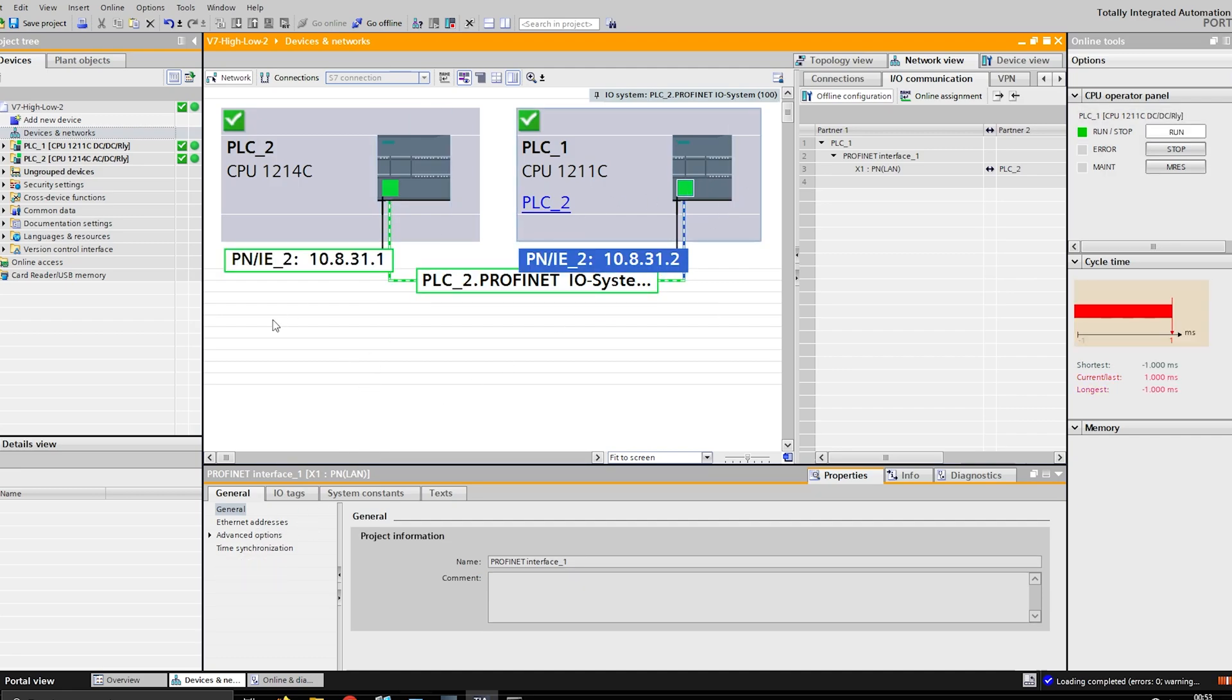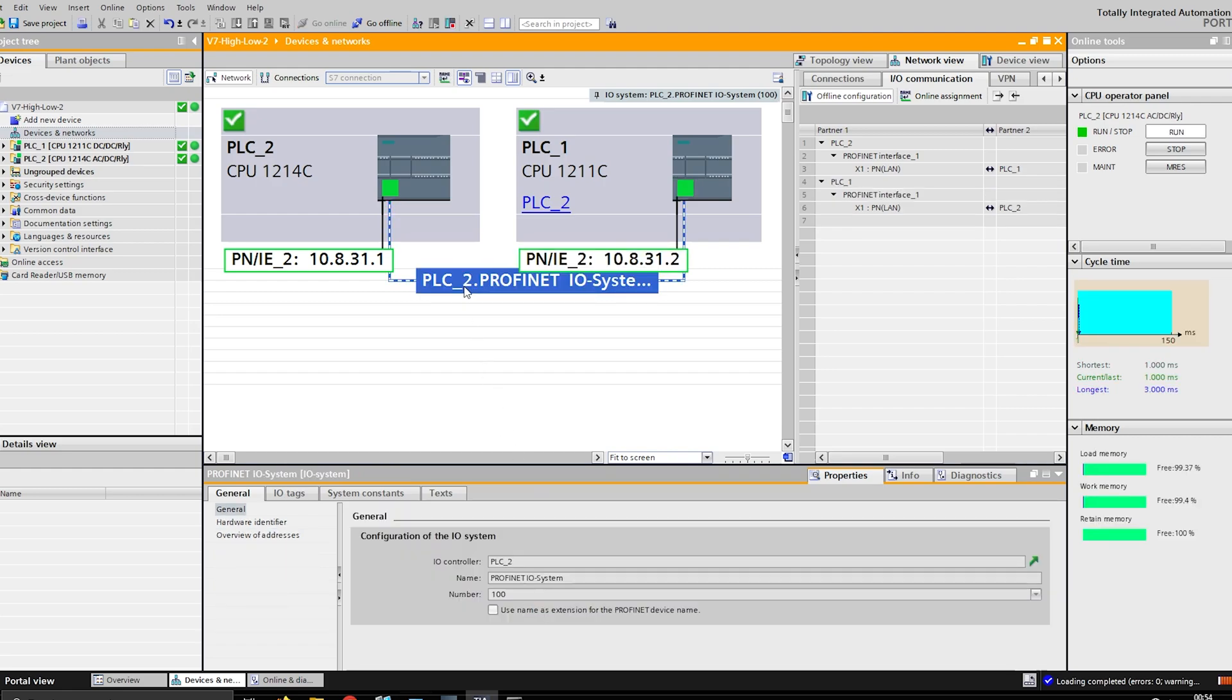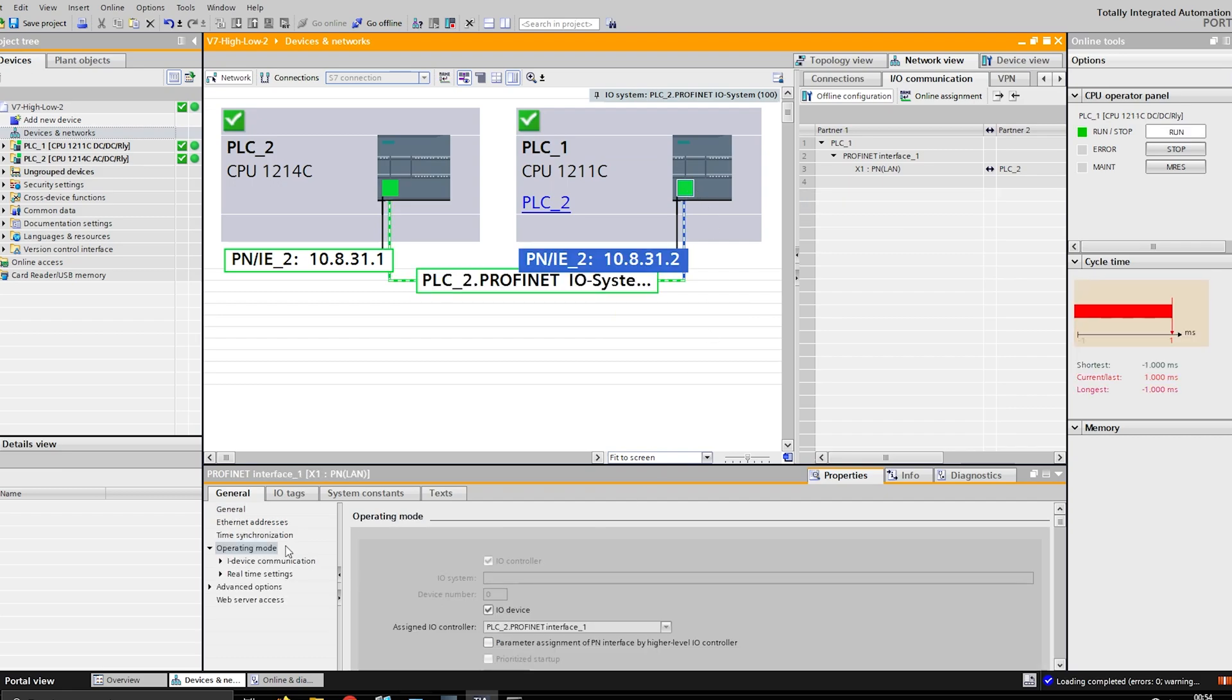So this one doesn't have web access like this one does, and it doesn't have operating mode. That operating mode is what you need to be able to get this communication working - this is at least the one way that I found. You go to operating mode on my old PLC, the 1211C, and then what I did was I set that to IO device, and then I assign it to the IO controller. These are grayed out right now because I'm online. I ticked this IO device and then set my network, which is this PROFINET IO System.